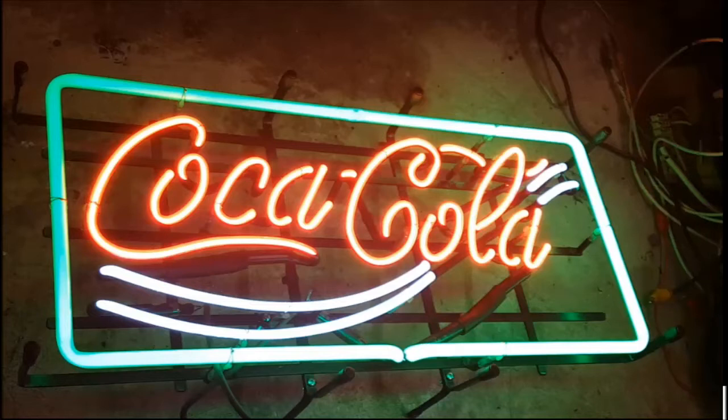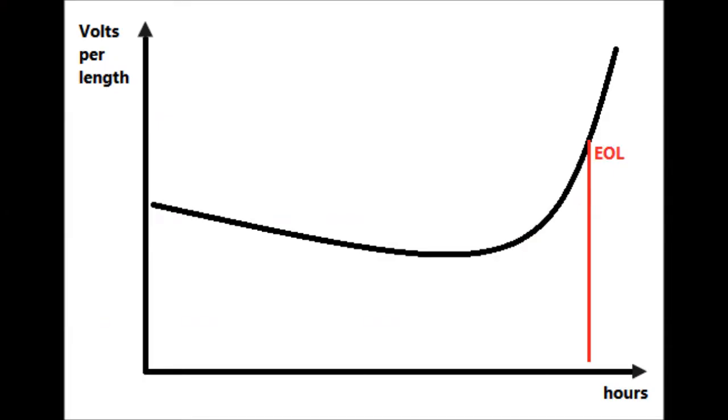One cause that I'm ruling out here is a loose connection. Another would be that the transformer is just too small for the tubing length so it doesn't have enough output voltage. Then another possible cause is one of the tubes has reached the end of its lifespan.